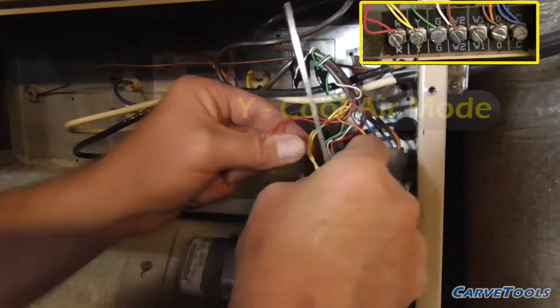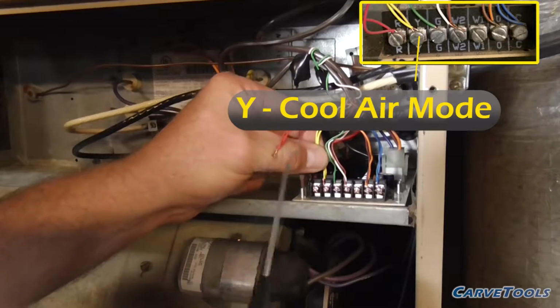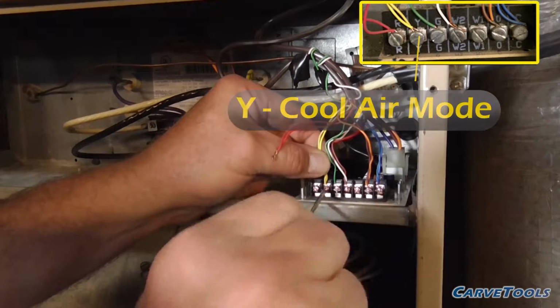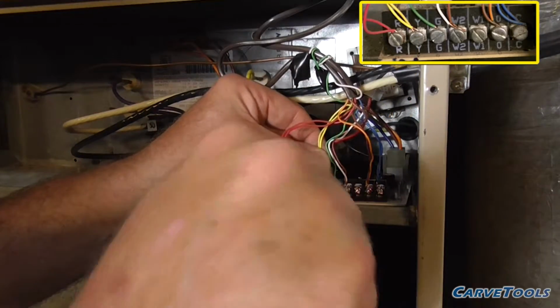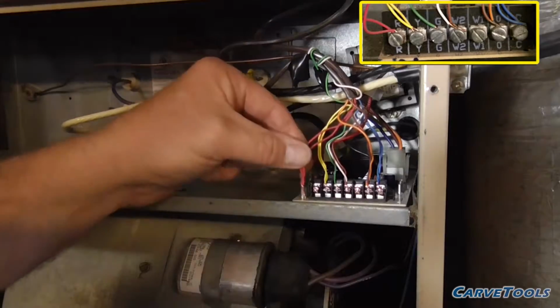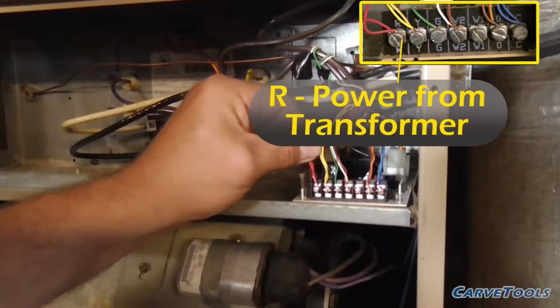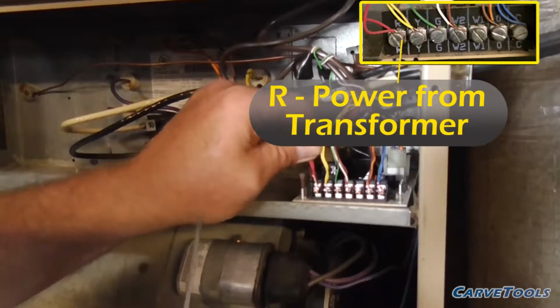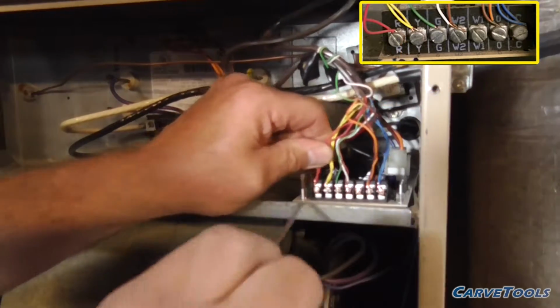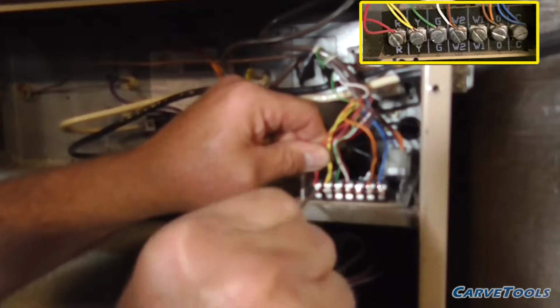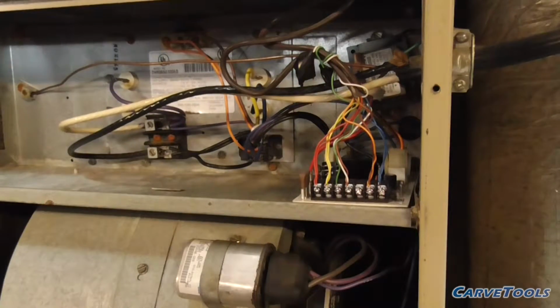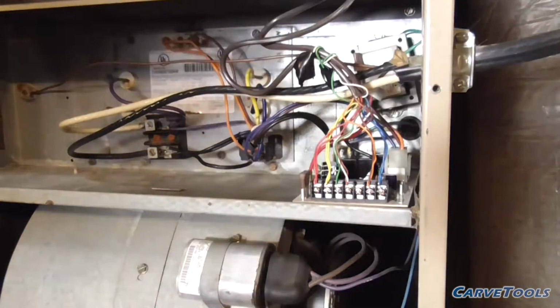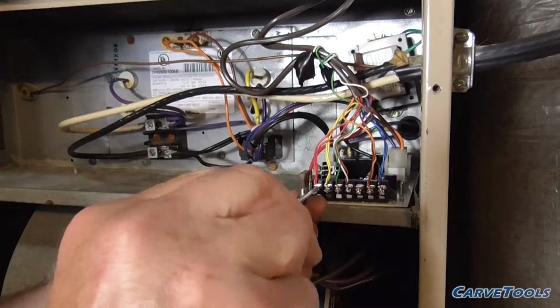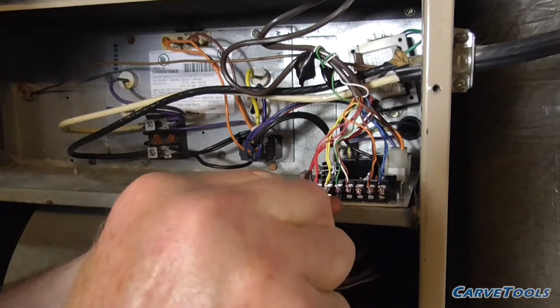The Y terminal is for cool air mode. That's what we want. There are two yellow wires, one from the thermostat and the other to the outside unit. The R terminal is power from the transformer. There are two red wires twisted together, one from the thermostat, the other to the outside unit. I'm going to double check the wiring. It all looks good. I'm going to go turn the circuit breaker on, and the fan should start running.